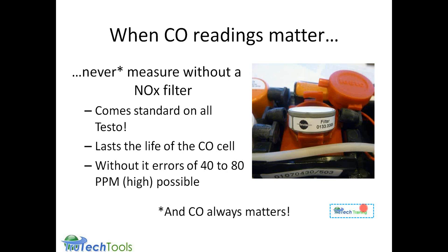Okay, here's the picture of the CO sensor with the NOx filter. This is what it looks like. It's in this little bayonet coupling that sits above the red sensor. This is the filter block itself. Basically, we advise you should never measure CO without a NOx filter. And it lasts pretty much the lifetime of the CO sensor. Without it, you can get errors in the range of 40 to 80 ppm or higher. So it's really something you have to pay attention to, that you do use a NOx filter when you do CO measurements.